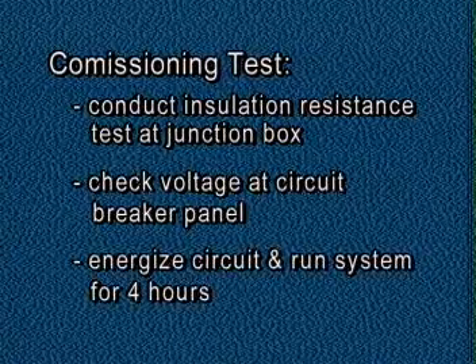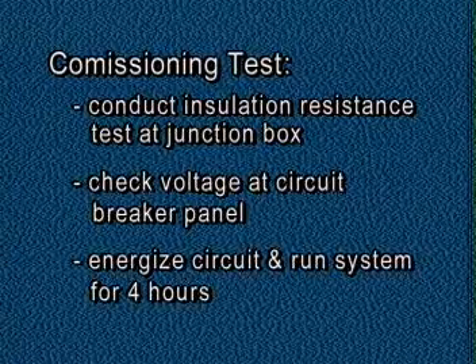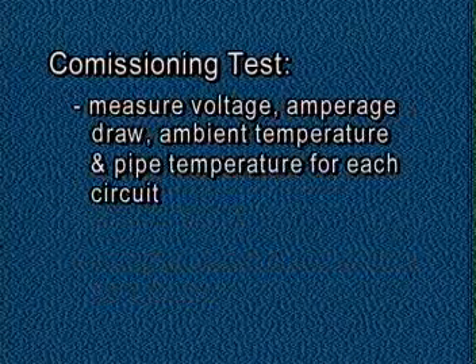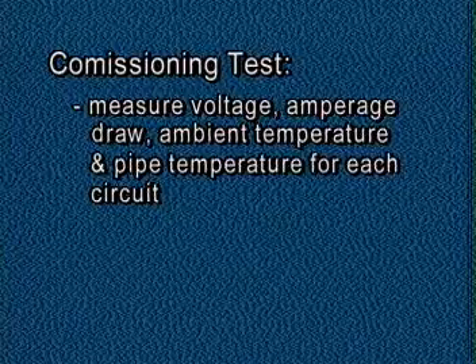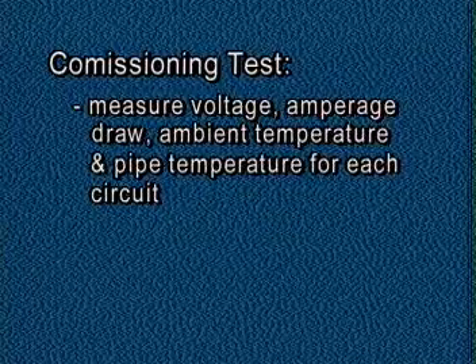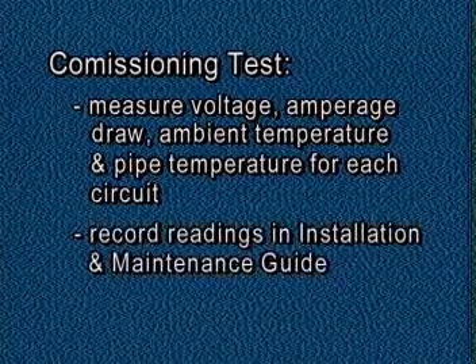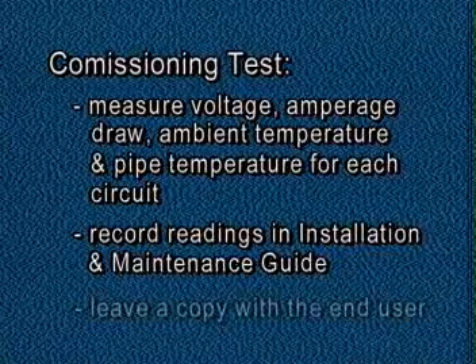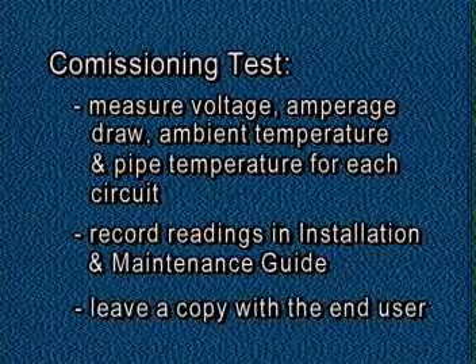Energize the circuit and allow the system to run for at least 4 hours to let the pipes reach a steady temperature. Finally, measure the voltage, amperage draw, and ambient temperature, as well as pipe temperature for each circuit, and record the readings in the installation and maintenance guide. Leave a copy of the guide with the end user.